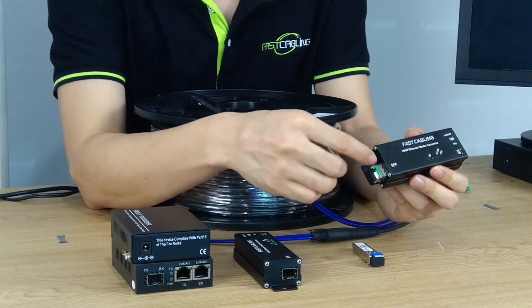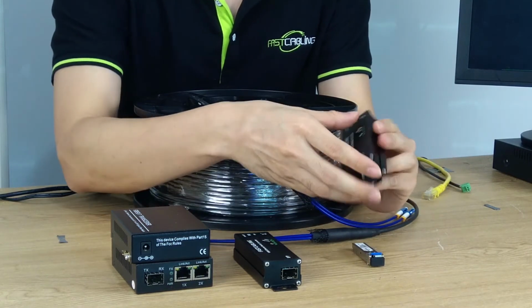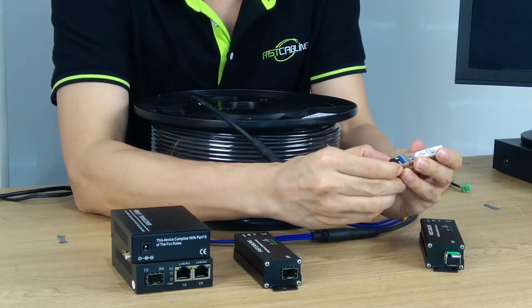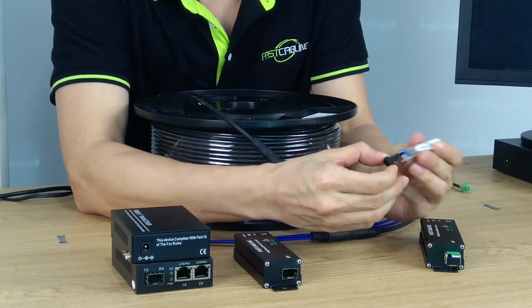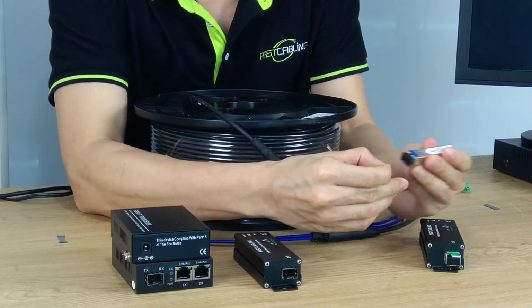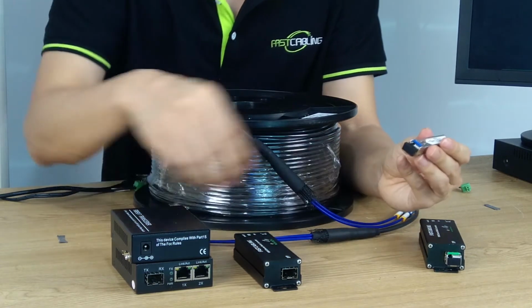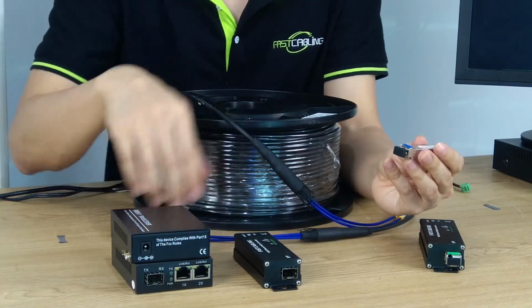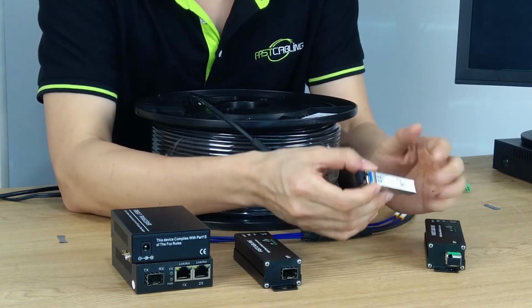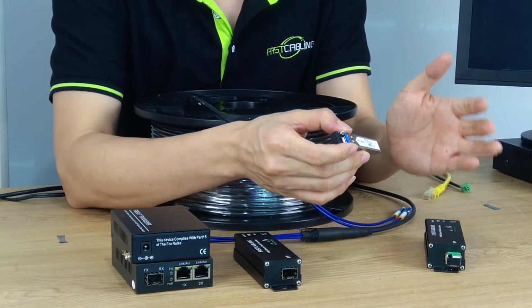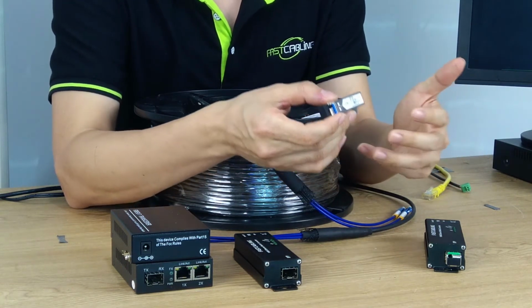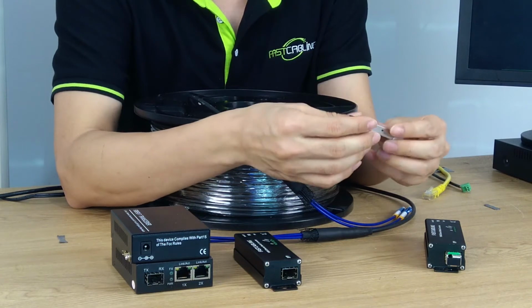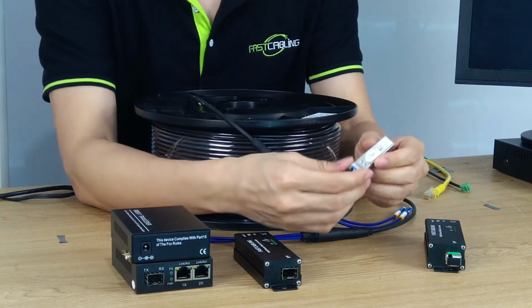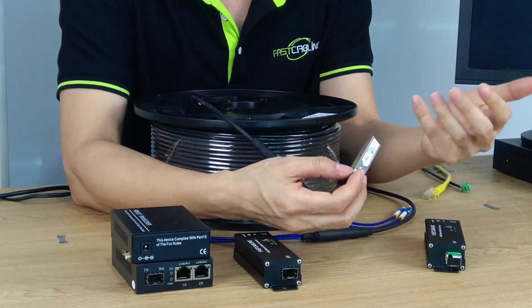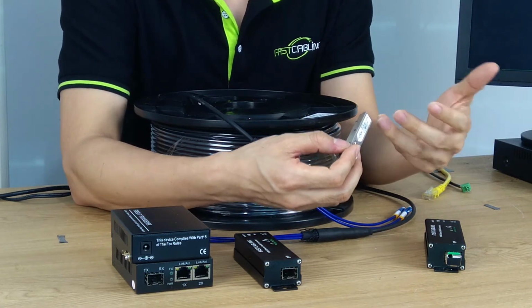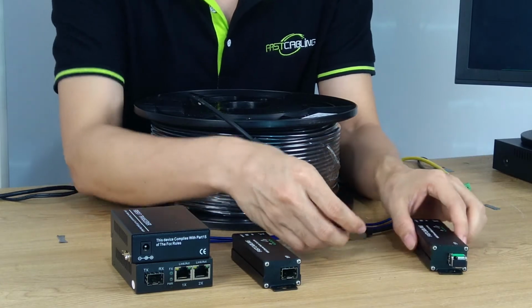You may ask why the fiber optic module is sold separately. That's because when you choose the fiber optic module, it determines what kind of connector you need—like this one, the LC connector for the small fiber optic cable. It also determines the distance: these two can provide a 20 kilometer fiber optic link, while other modules can provide up to 80 kilometers. It also determines the fiber optic type—it decides everything. Different applications may require different products, which is why they're sold separately.